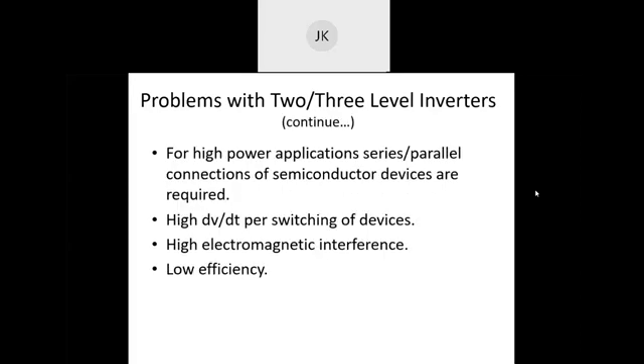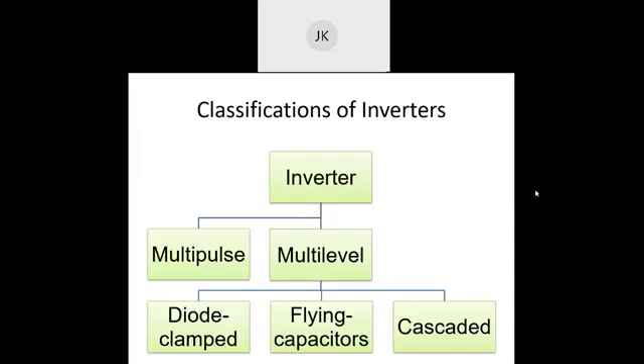Another problem is the continuous high dV/dt, because for 2 or 3 level voltage, when the switch is on, voltage is 0, and when the switch is off, voltage across the switch is maximum. So when the switch is turned on and off, the change in voltage is very high for 2-3 level inverters. But if we go for the multi-level inverter, the voltage across a particular switch is not the full supply voltage. So dV/dt is less, which produces less electromagnetic interference, and efficiency also improves because switching losses are reduced.